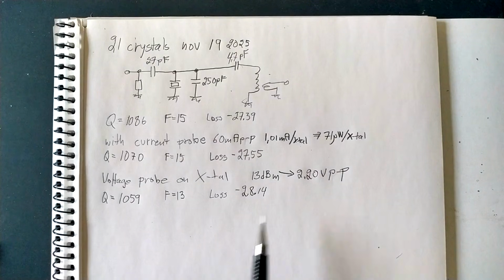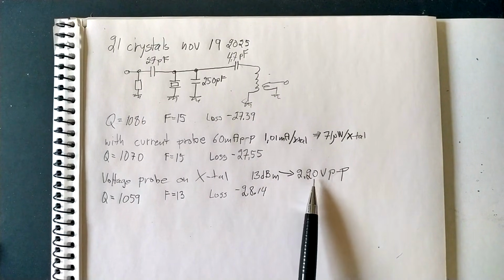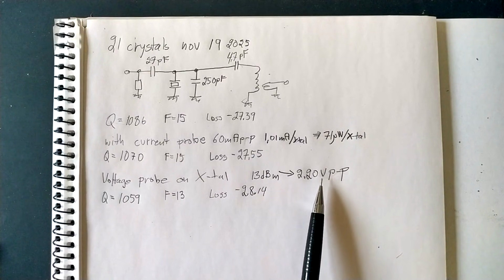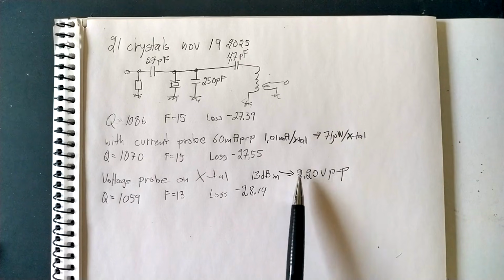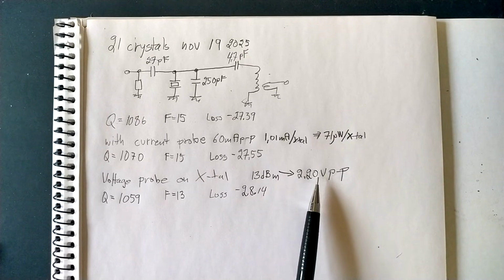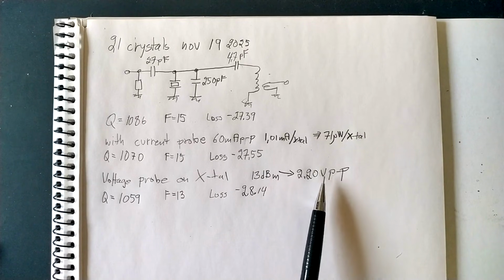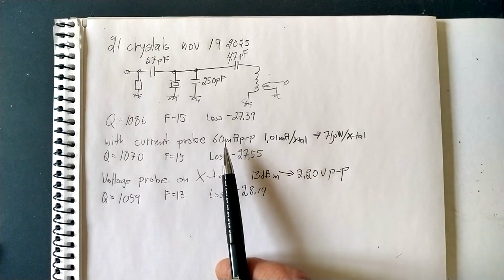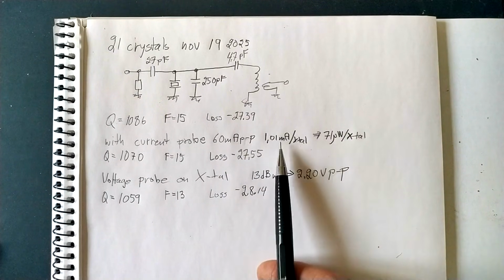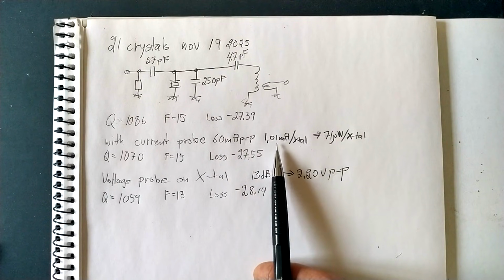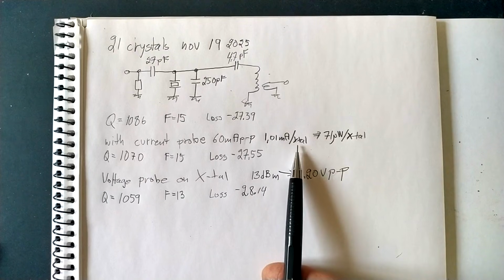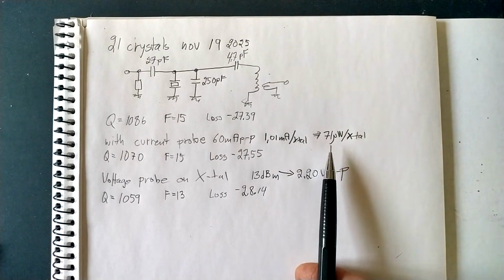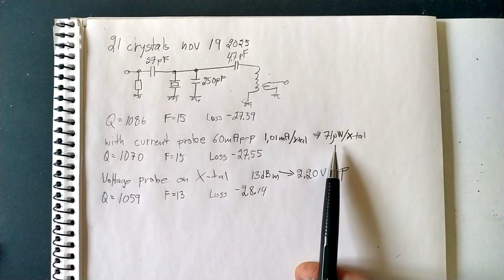The voltage probe gives me 2.20 volts peak to peak, and I want more to have a good low noise at wide offsets. The flat noise floor goes down when I have a larger voltage here. The current is 60 milliamps peak to peak. That gives 1.01 milliamp RMS for each crystal, and that gives me 71 microwatts per crystal.